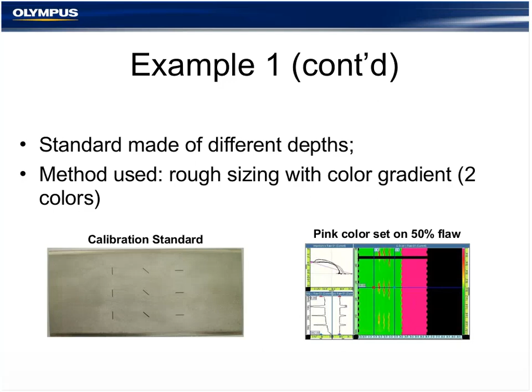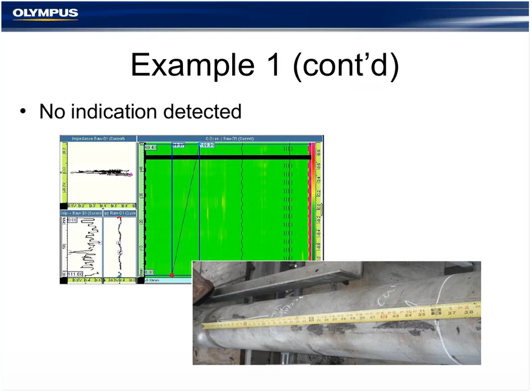So again, this was one of the numerous examples where there was no flaw detected. And for those who may ask, what is that black horizontal bar on the top? It was one of the coils. If I go back to the previous slide, during the calibration, it's easily determined with that wide notch that I was showing earlier whether I have a coil not working, and the OmniScan allows you to turn that coil off for inspecting if that happens. So that's what happened there. There was a broken coil on the array.